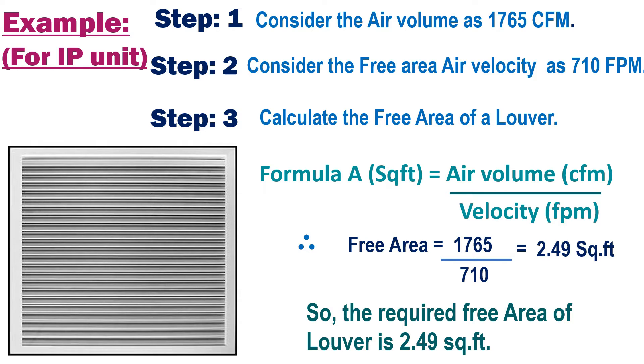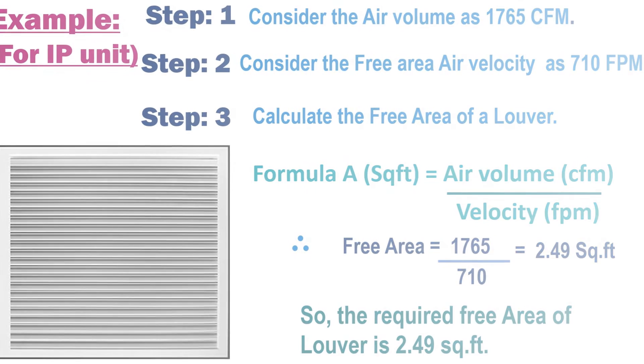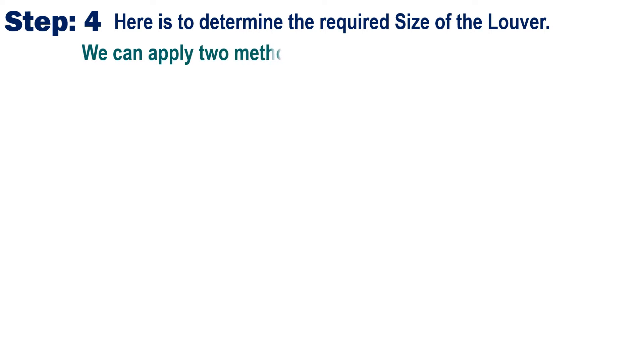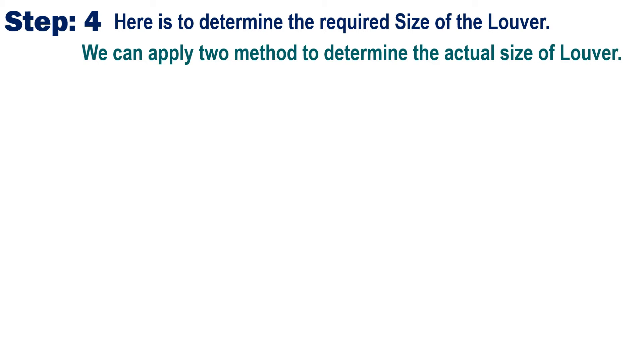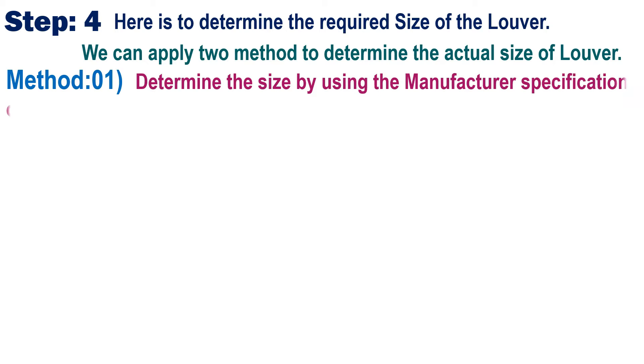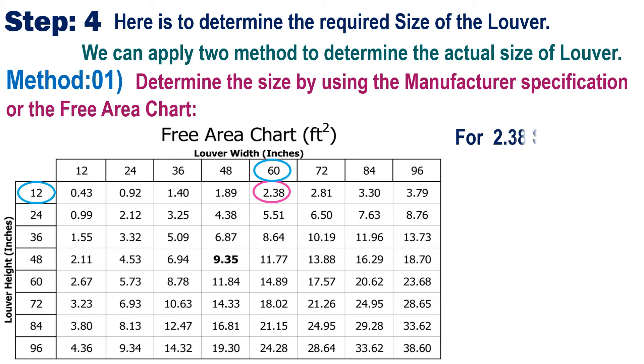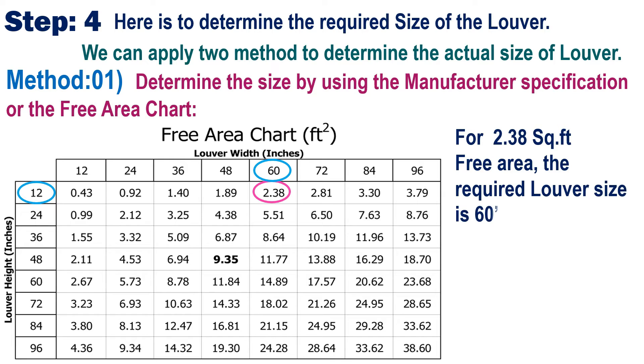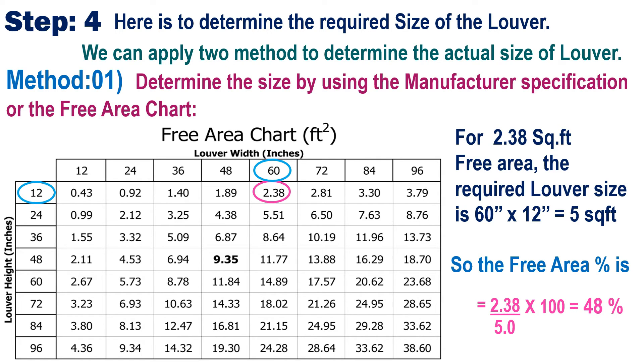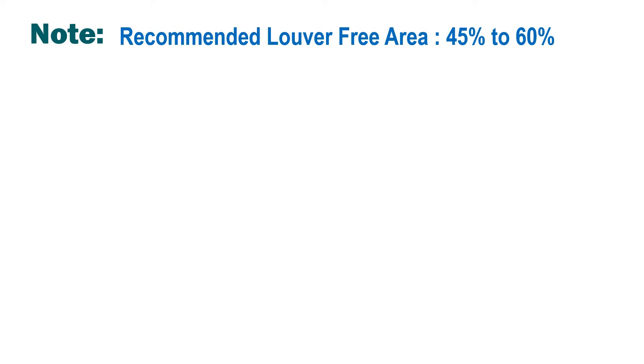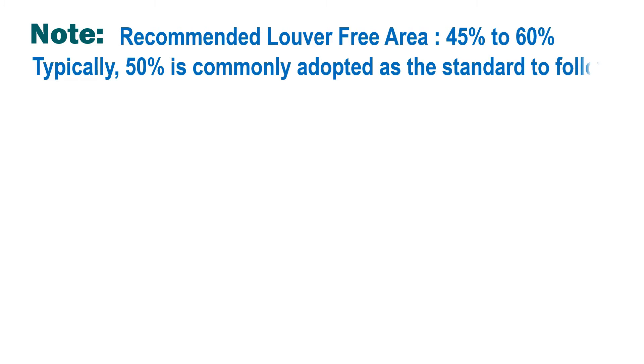So the required free area of the louver is 2.49 square feet. Now, here is how to determine the required size of the louver. We can apply two methods. Step 4, first method: determine the size of the louver using the manufacturer specification or the free area chart. For 2.38 square feet of free area, the required louver size is 60 inches × 12 inches = 5 square feet, so the free area percent is 48%. Note: the recommended louver free area is about 45% to 60%; typically 50% is commonly adopted as the standard rule of thumb.